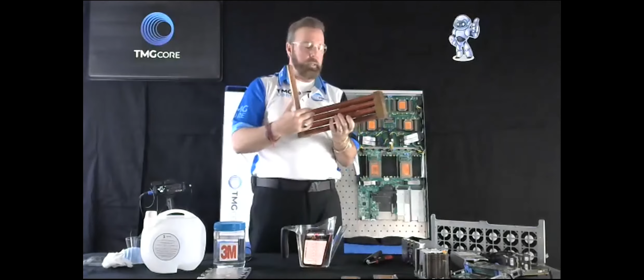Then you supply warm water, actually hot water, whatever you define as hot or warm, 90-degree F water in, so it's not chilled water. We push it through the different coils, as you can see here, and then it gets removed. We take it to a secondary final heat rejection, which is a closed loop system. It can be either, and it doesn't have to be water, by the way. It can be a refrigerant, whatever cooling medium you want to use. Water is cheap for most cases. You add a surfactant so it doesn't scale up inside, because you get heat degradation or heat transfer loss from scaling, minerals in the water. So we add surfactants, detergents, and so on, and it's a closed loop system.